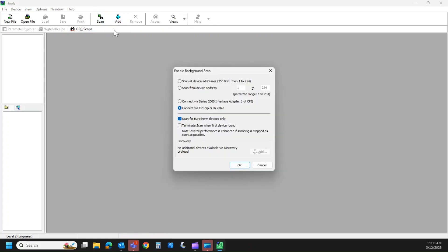So when you're connected with the CPI clip or configuration cable, you're going to plug one end into that port on the back of the Mini 8 and the other end just goes into your USB on your PC. We're going to come up here to scan, and the fourth selection down is connect via CPI clip or IR cable. So we're going to select that and we're going to hit OK.